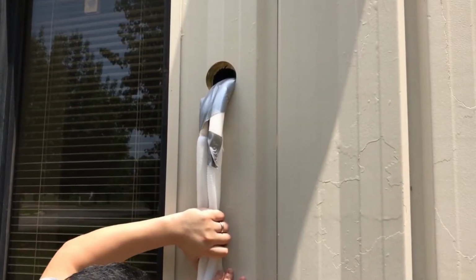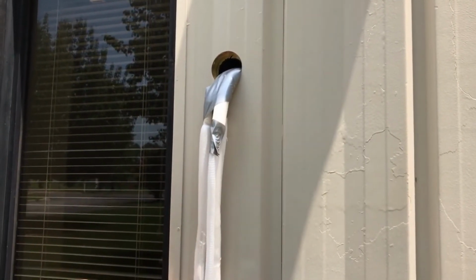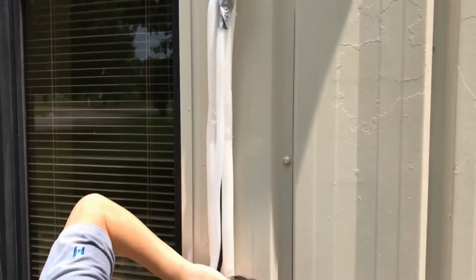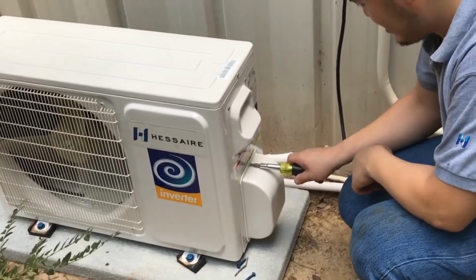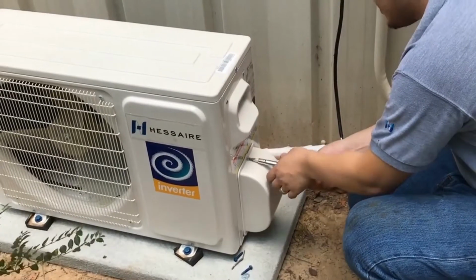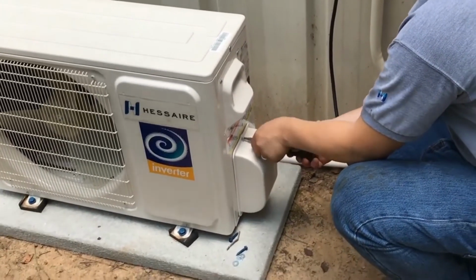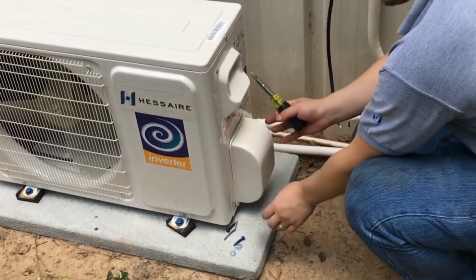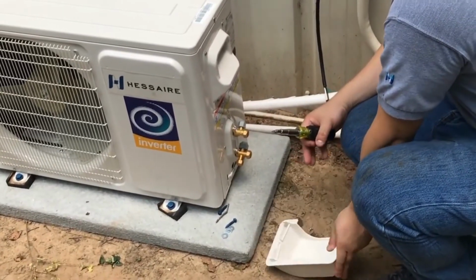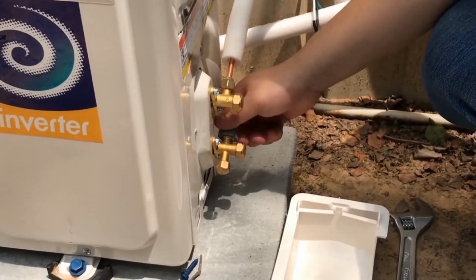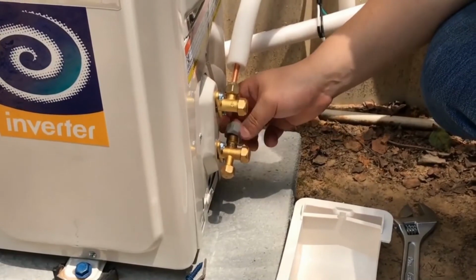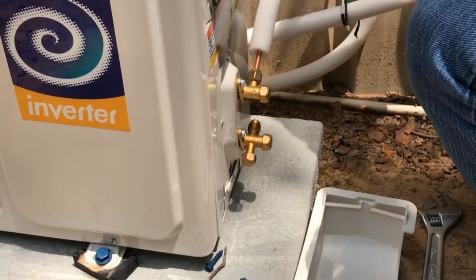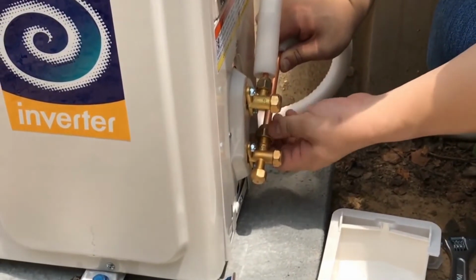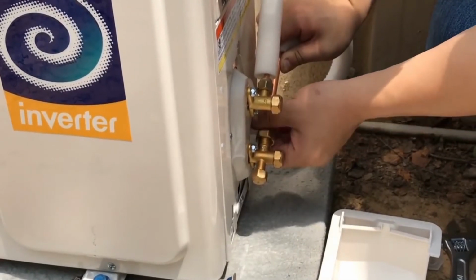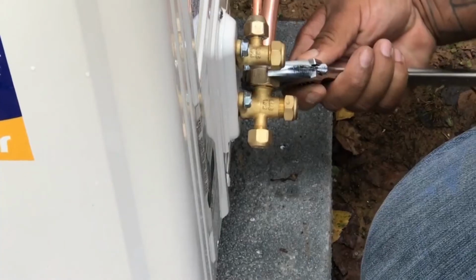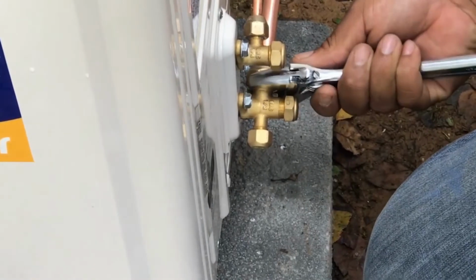Carefully bend the tube bundle to be flush with the wall, making sure not to crimp the copper or drain tubing. Next, remove the panel that covers the refrigerant valves and wiring connections. Remove the protective screw caps from the valves. Now you can connect the pipe joint of the outdoor unit to the copper line set. Start the union nut by hand, then use the torque wrench tightening to the specifications in your manual.